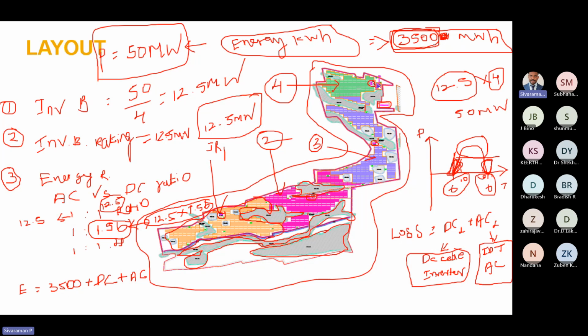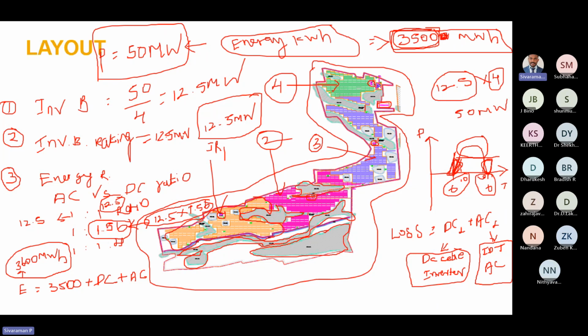So now the energy requirement is no longer 3500 megawatt hour. By considering the DC and AC losses, the energy requirement may increase to 3600 or 3700 megawatt hour. This is the total energy requirement considering the losses. As I told, the 1 versus 1.56 has to be taken care of considering the losses in the system. It includes the DC cable loss, inverter loss, AC cable loss, inverter duty transformer loss, power transformer loss in the substation, and the transmission line between the substation and the interconnection point. Like this, we have to consider the AC versus DC ratio.